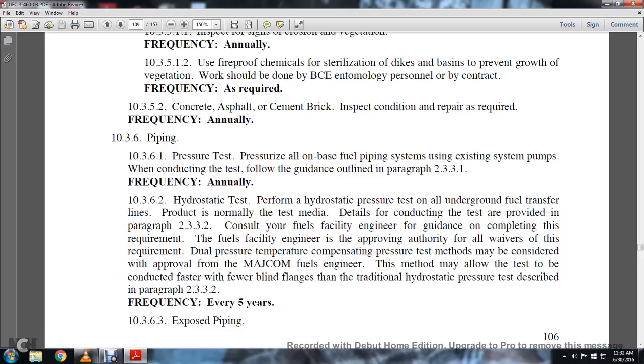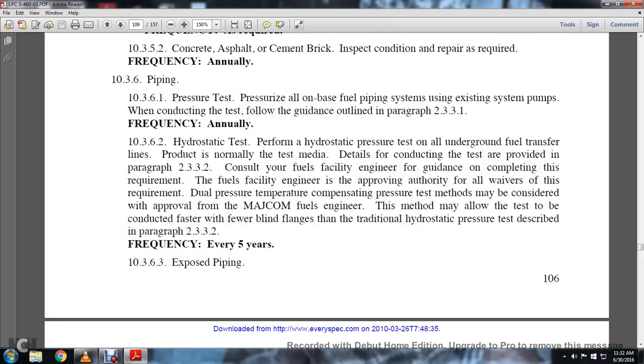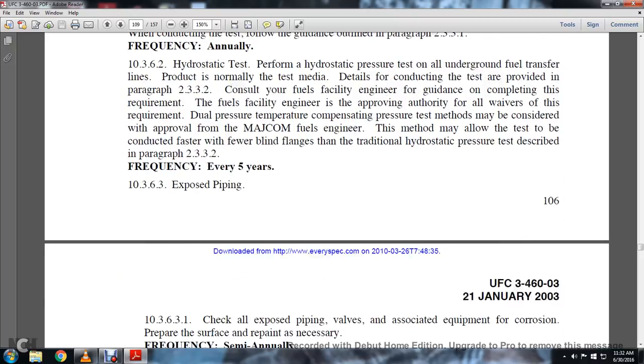Dual pressure temperature compensating pressure test methods may be considered. With the approval of the MAJCOM fuels engineer, the method may allow the test to be conducted faster and with fewer blinds than the traditional hydrostatic pressure test described in 2332. Every 5 years. Exposed piping.